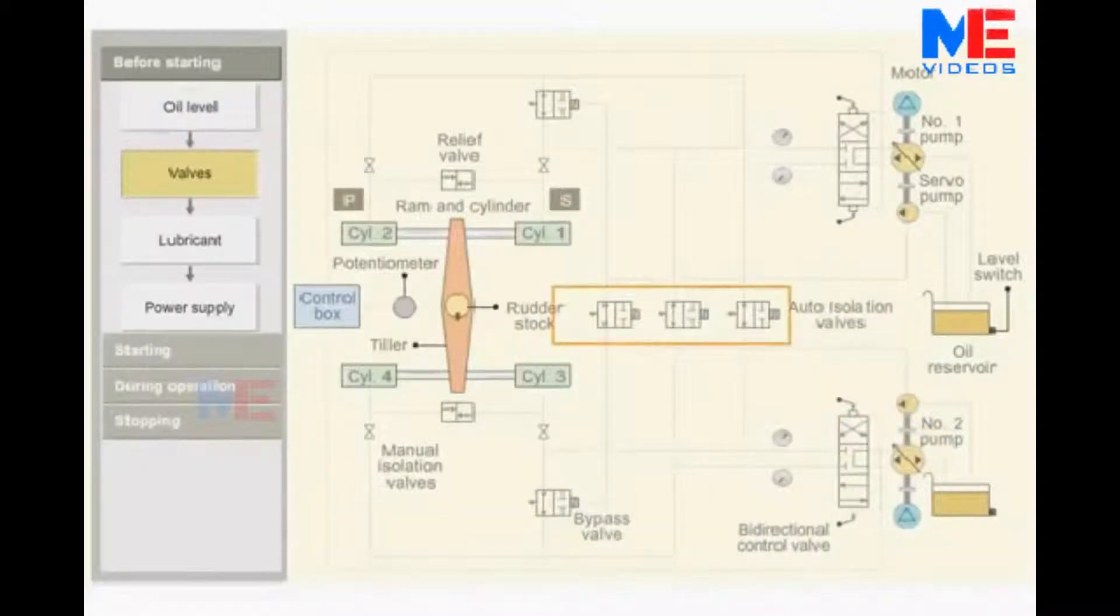Check whether the manually operated isolation valves are in open position. If they are shut inadvertently, it will affect the ram movement.